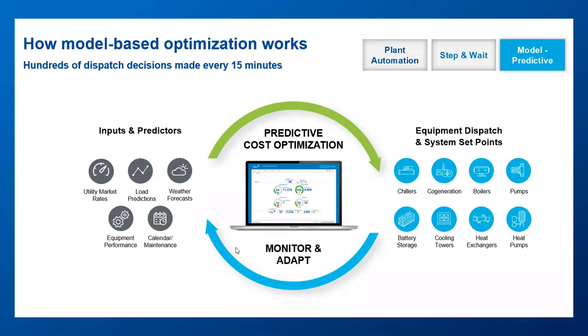Another advantage is that when you set a minimum dollar value as the mathematical objective function, the approach can be flexible enough to solve not just for energy in total BTUs but for other goals as well. If you put everything into dollars, the system can solve based on how you weight those different goals, things like water cost, peak demand charges, time-of-use rates, demand response revenues, and even the cost of carbon if your organization uses that internally to justify the business case for investments.